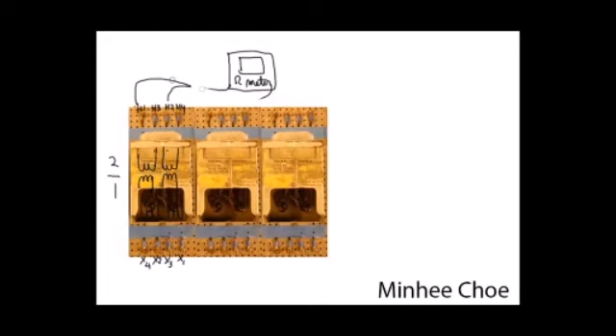So you'll do an ohm reading between H1 and H2. Then you're going to read the ohm for H3 and H4. At the same time, you'll do the same thing for the secondary transformer coil by reading these two and these two.